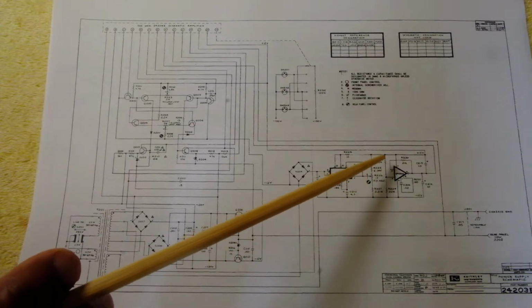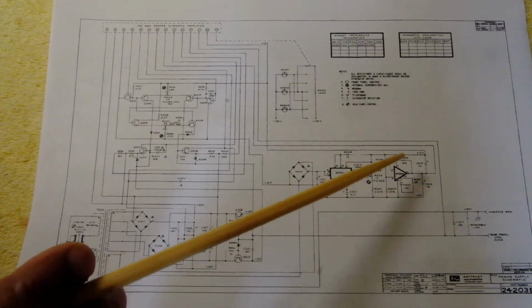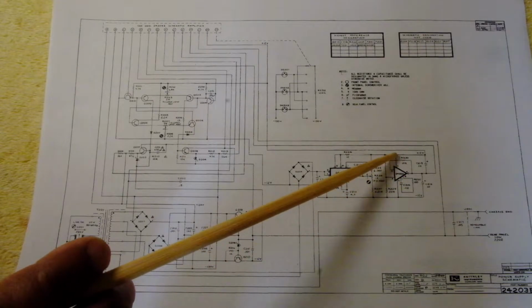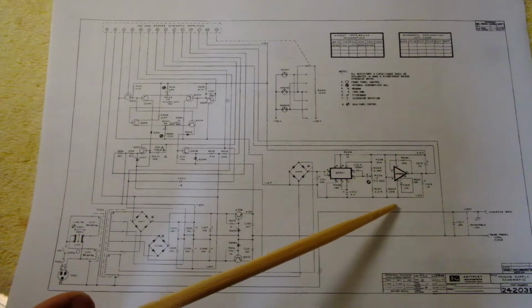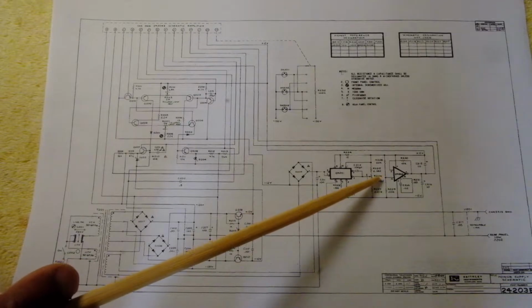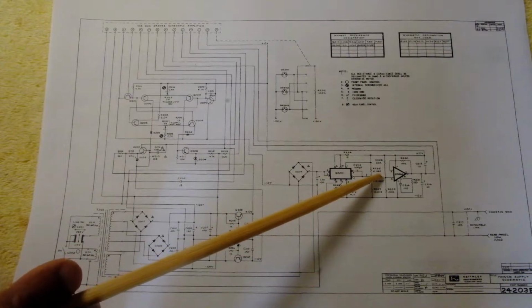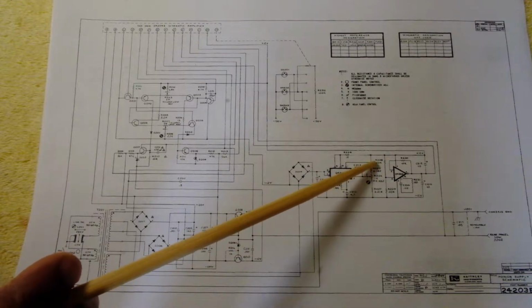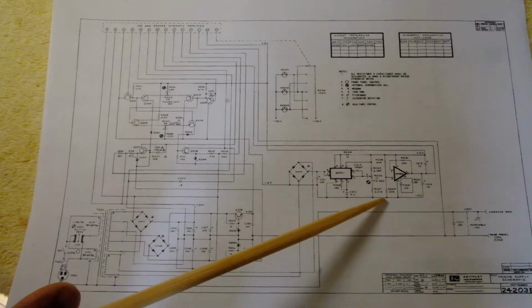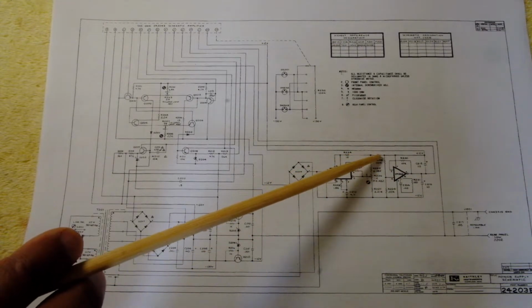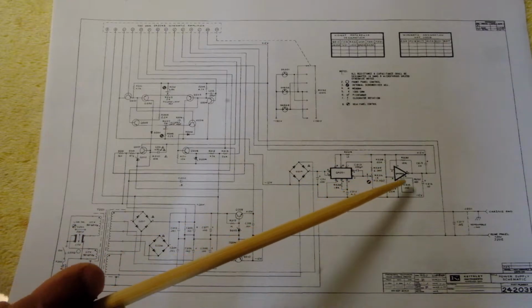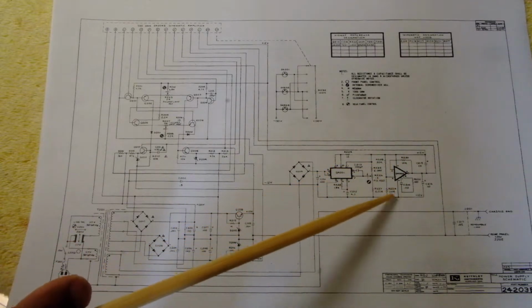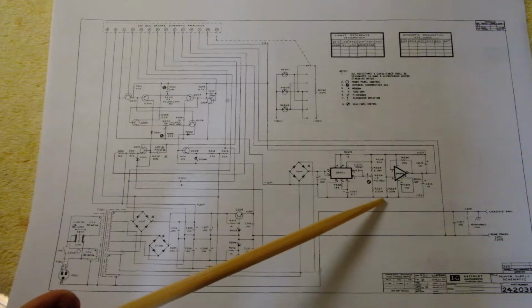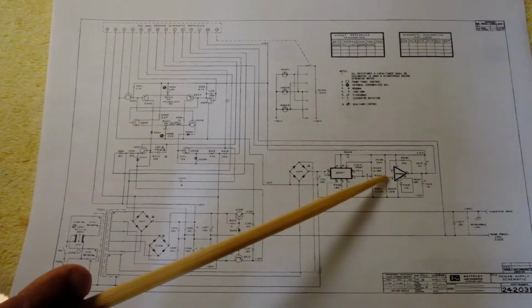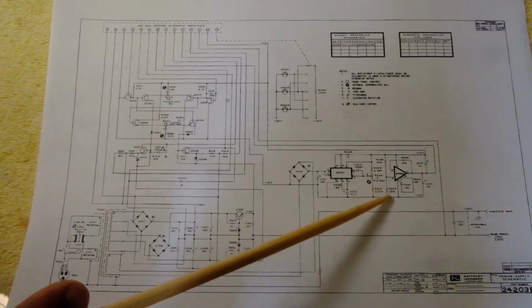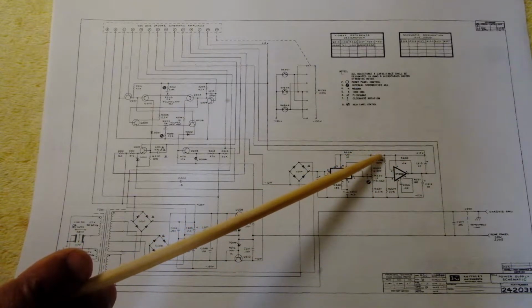and that is then converted to a differential output in terms of polarity, to a plus and minus 12 volt supply output, using this amplifier. The positive input of this amplifier is biased halfway between these two. So if this is 0 volts, this will be 24 volts. But the way it's configured, with the feedback and the way this is connected, this generates 0 volts at this point, and this becomes minus 12 and this becomes plus 12.